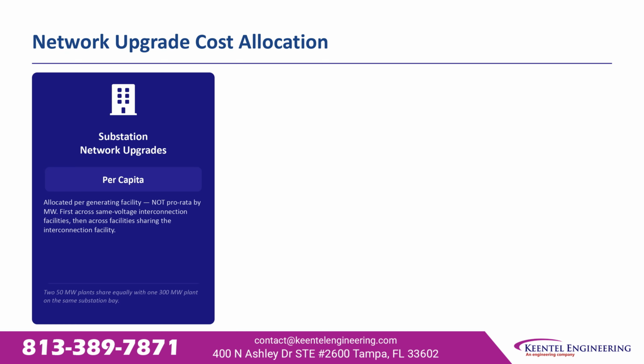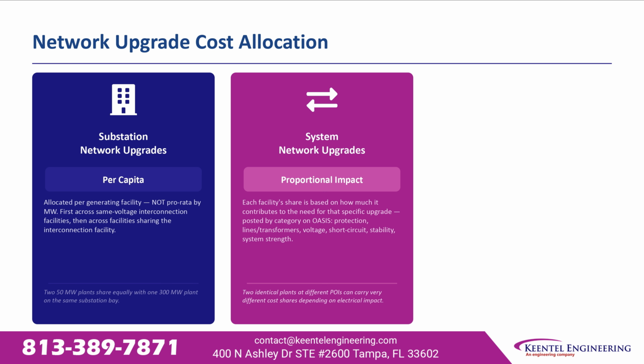There are 3 upgrade categories and 3 allocation methods. Substation network upgrades split per capita per generating facility, not by megawatts — two 50-megawatt plants share equally with one 300-megawatt plant at the same substation bay. System network upgrades allocate by proportional impact: each facility's share reflects how much it drives the need for that specific upgrade, posted by category on OASIS. Two identical plants at different points of interconnection can carry very different shares.